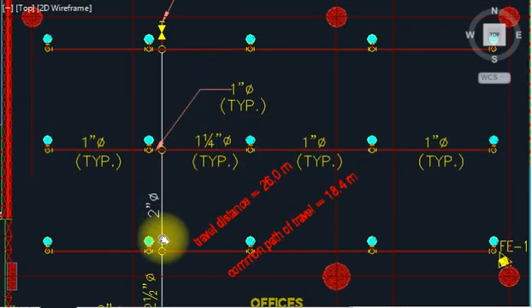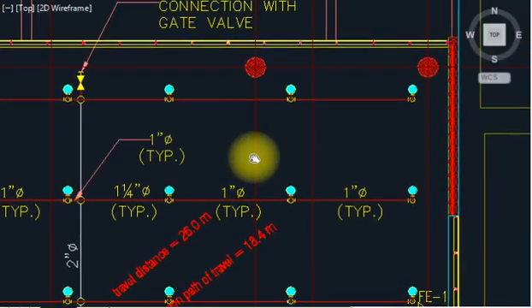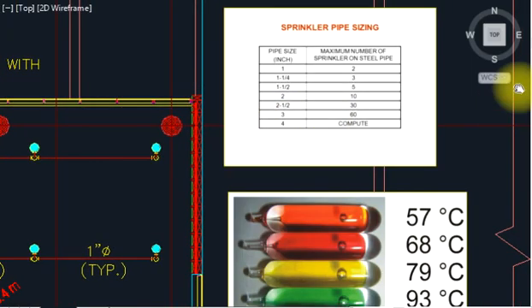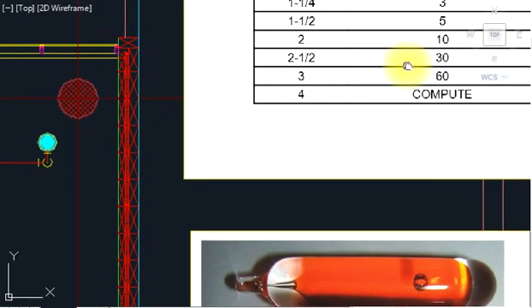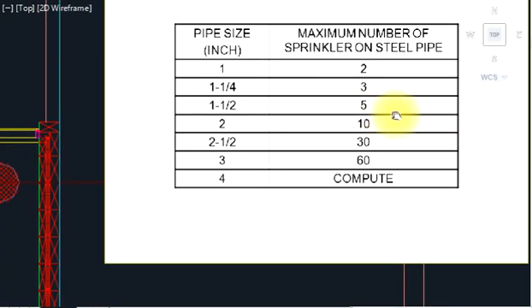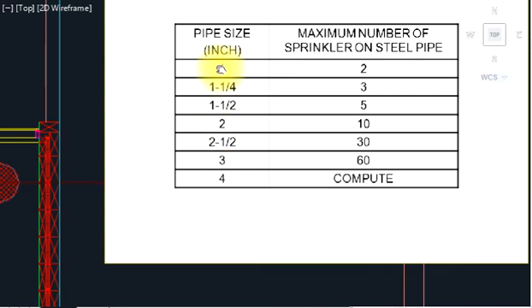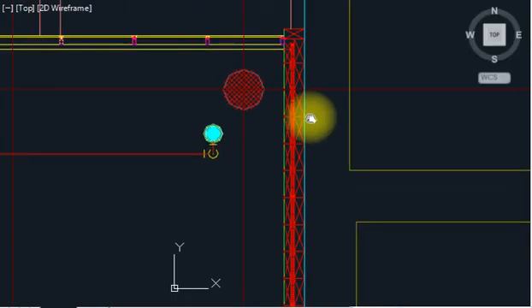When you reach 10 sprinklers, the pipe will be covered by 2 inches. I will show you the thumb rule chart — keep this in mind as interview questions often ask about it. The rule is: 1 inch pipe = 2 sprinklers; 1 and 1/4 inch = 3 sprinklers; 1 and 1/2 inch = 5 sprinklers. The pipe diameter is in inches — 1 inch equals 25 millimeters, 2 inches equals 50 millimeters.